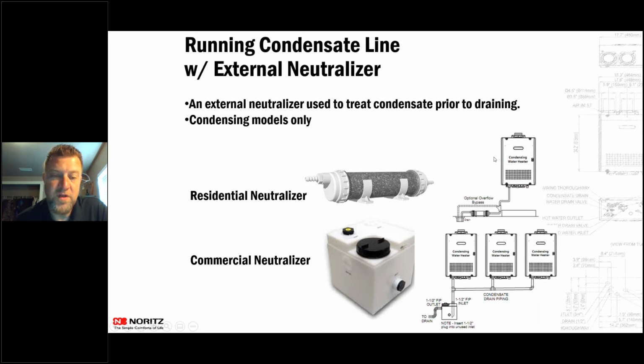So if you have just one unit, you can use those residential neutralizers. If you have multiple units, like you're putting it in a large install like we have up at the VA hospital, we do make a commercial neutralizer. Everybody makes a commercial neutralizer where you can run all of those together into that commercial neutralizer and send it out. So I know in Denver, the inspectors actually use litmus paper and actually test the condensate coming out of those units to make sure that you are neutralizing the acid in those units.